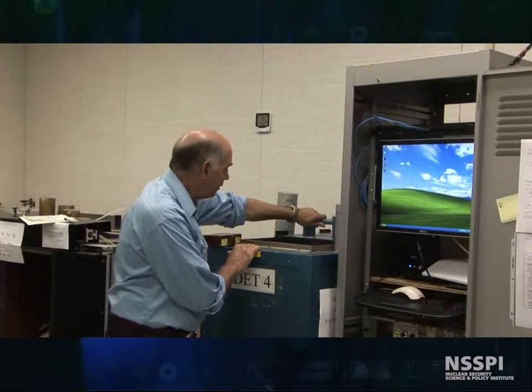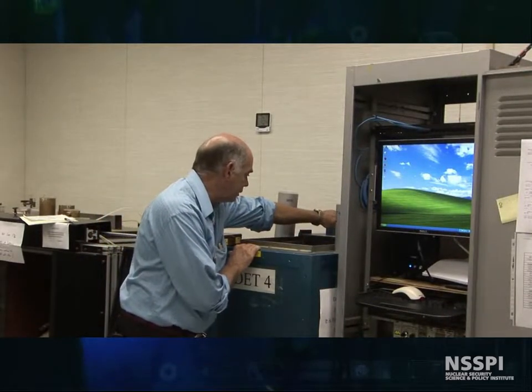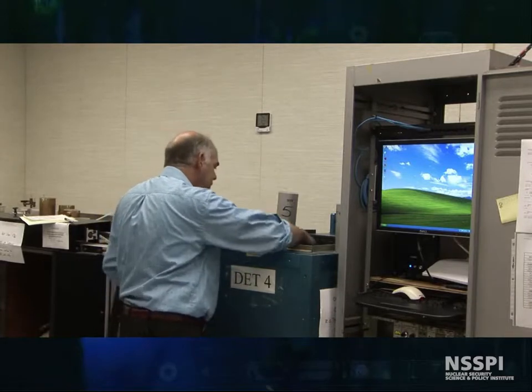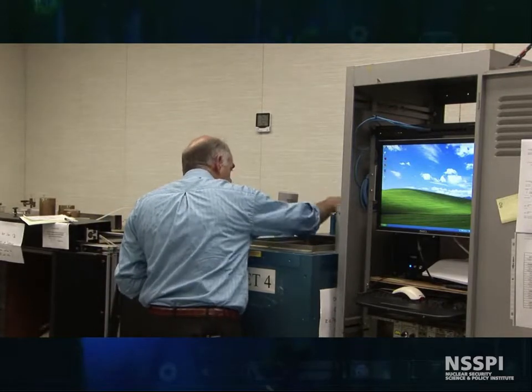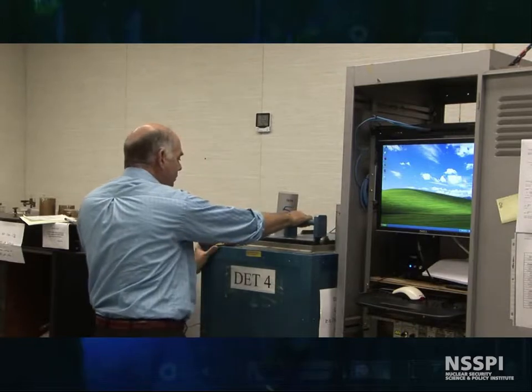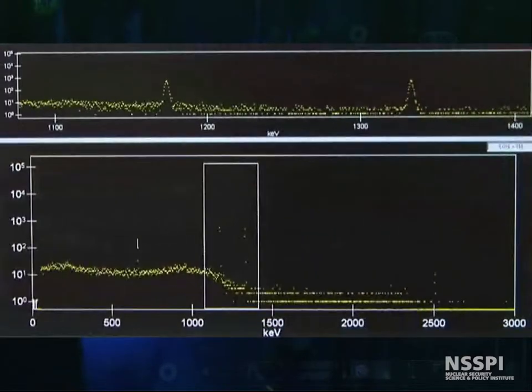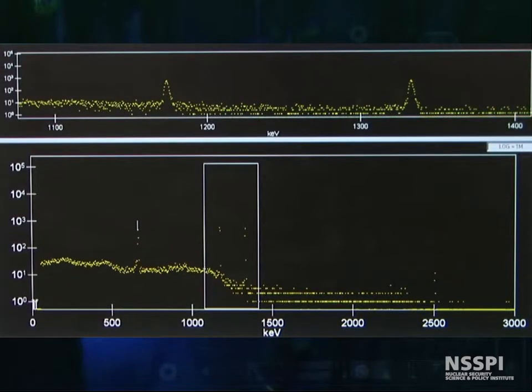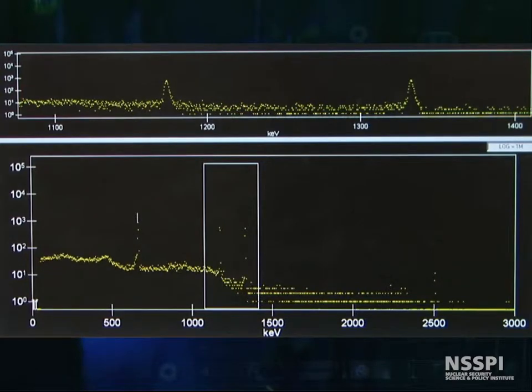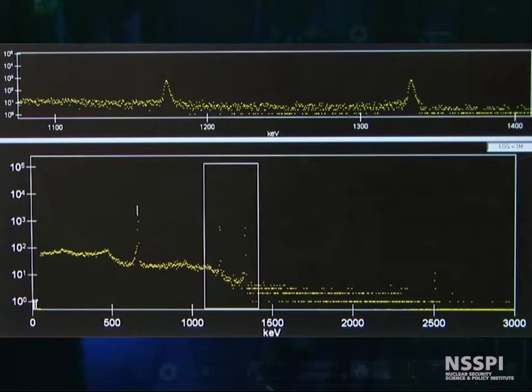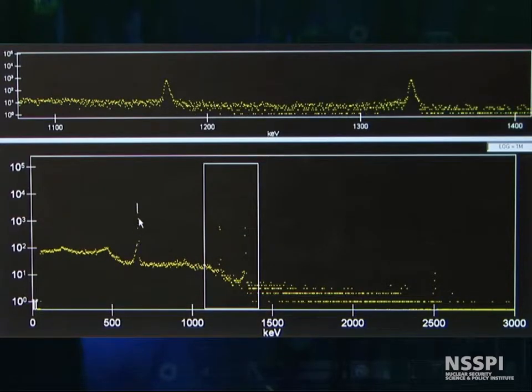Now we've got cobalt-60. I can add my cesium source. Again, I know the geometry, and we can go look and see how the cesium grows in. Now we see the cesium growing in too. So we have energy calibration points here, and we will use these points and construct an energy calibration.